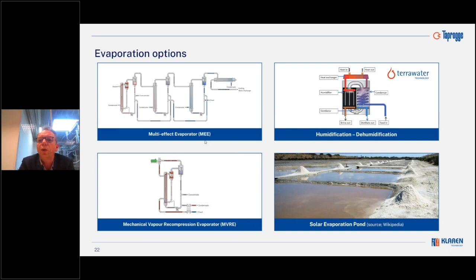On the left side, we see two systems with evaporation by a medium of steam or by a compressor. When you talk about steam, it would be a multi-effect evaporator plant. I will discuss that in detail, but it means that you use a heating medium to evaporate the water. And then in a sequence of effects, you can make this more efficient, but more about that later. The second alternative is not to use steam, but to use a compressor, where we use electrical energy to evaporate the water, but at the same time also condense it. The options on the left, I will discuss them in more detail right now. So we can also go to the next slides.